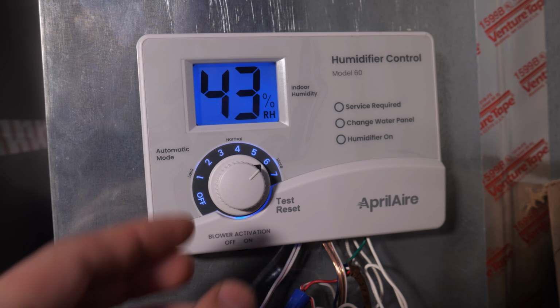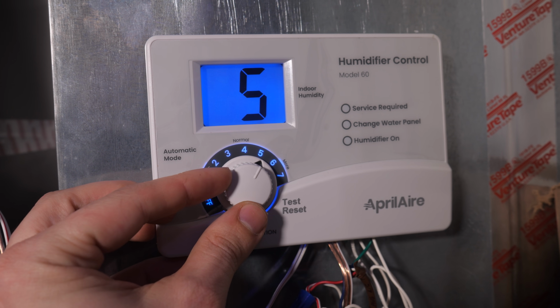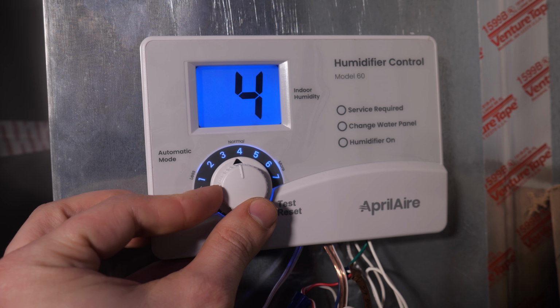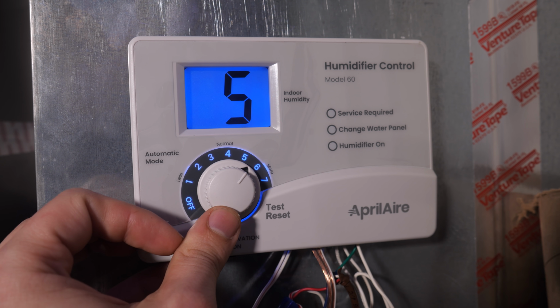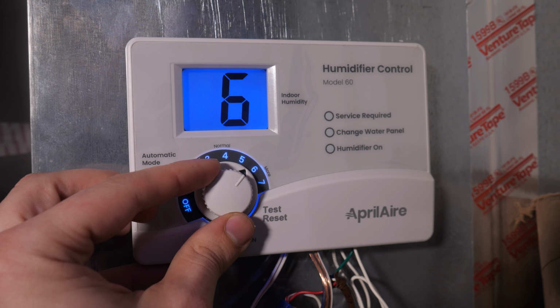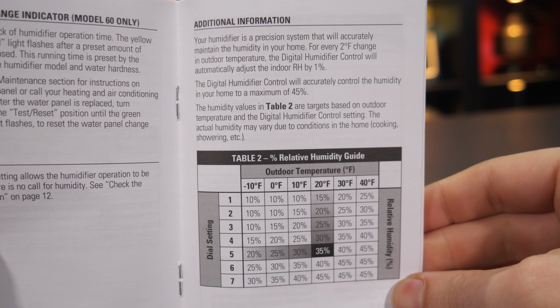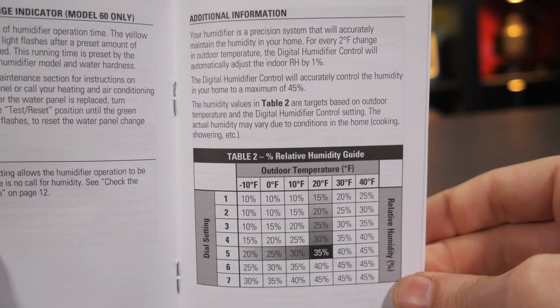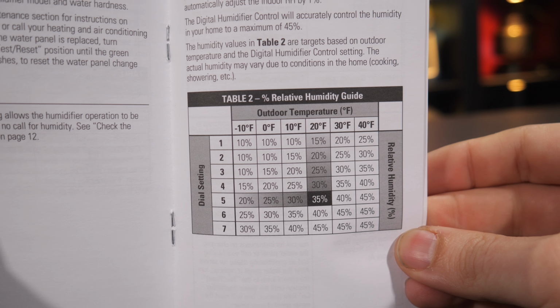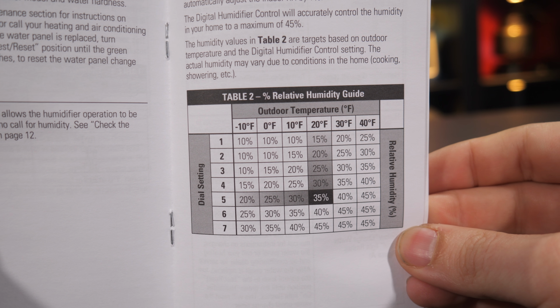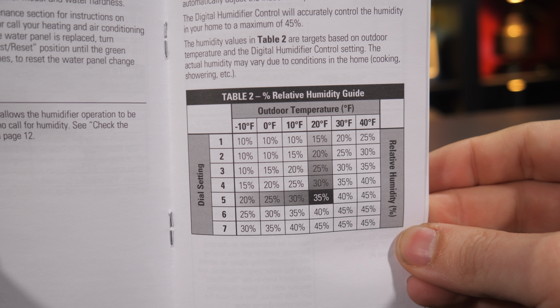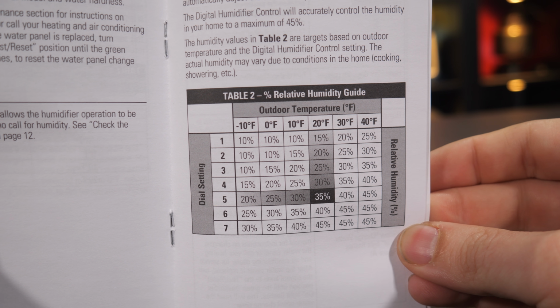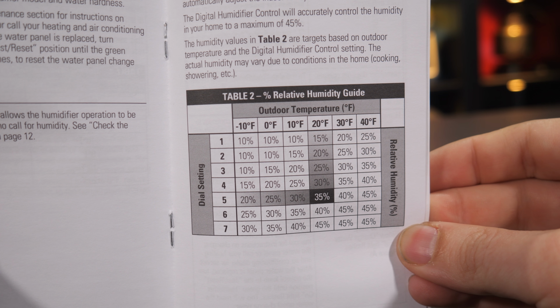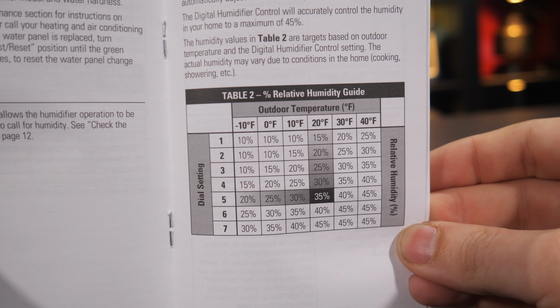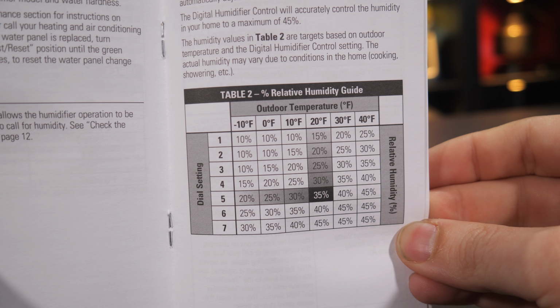But now that this control knows what the outdoor air temperature is, I no longer have to think about that. It will automatically reduce the humidity set point as the ambient temperature outside falls. This chart here explains how the humidifier will adjust the set point based on the outdoor temperature reading. The recommended setting, 5, will allow the humidity to get as high as 45%, but will start lowering it when the outdoor temp is 30 degrees Fahrenheit, which is just a hair below freezing.